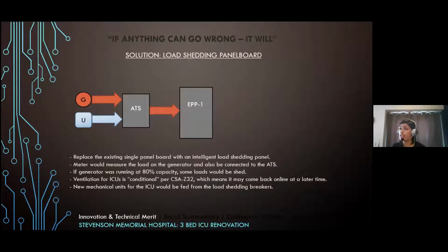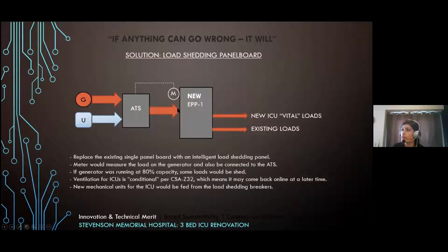emergency electrical panel. Our idea was to replace that panel with a new panel board, refeed all the existing emergency loads and their new vital loads from the new panel, but we would also install a meter on the panel board. The meter would be connected to the ATS and monitor the load on the generator. If the generator load started to reach its capacity, we would shed some of the less important loads from the panel. And we established that ventilation for the ICU was classified as conditional according to CSA Z32. So we were able to put conditional loads on these load shedding breakers, effectively creating a conditional branch of power in the hospital that wasn't there before, and allowing us to salvage some of the capacity of the generator.